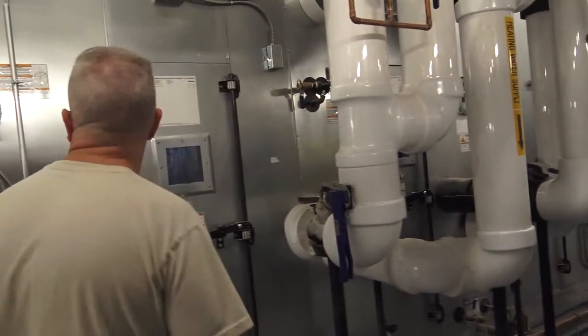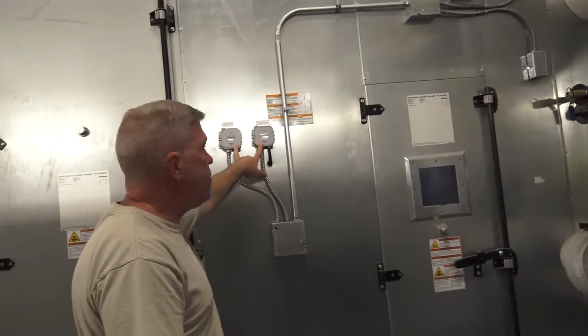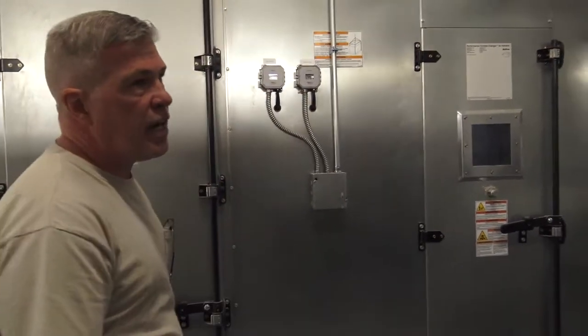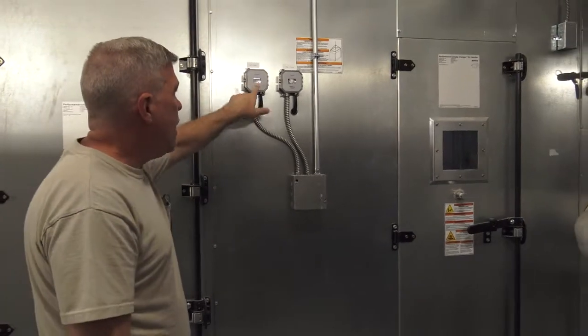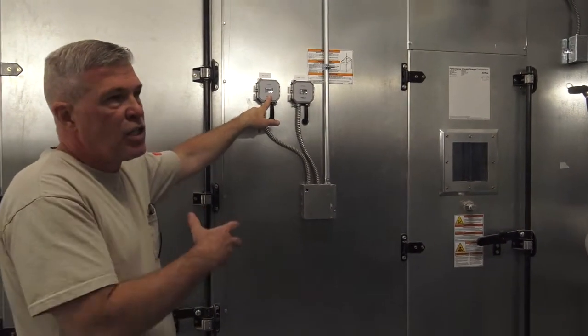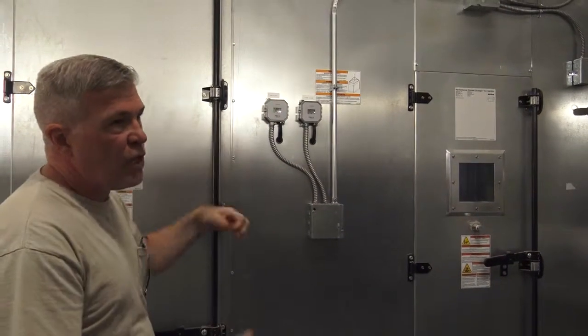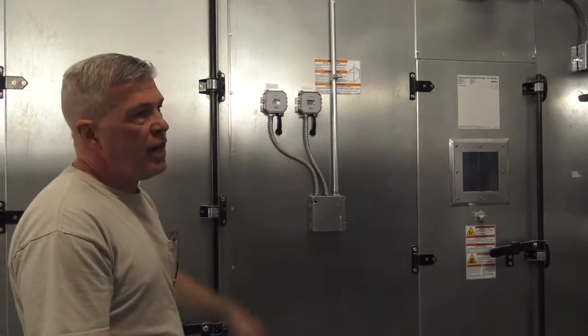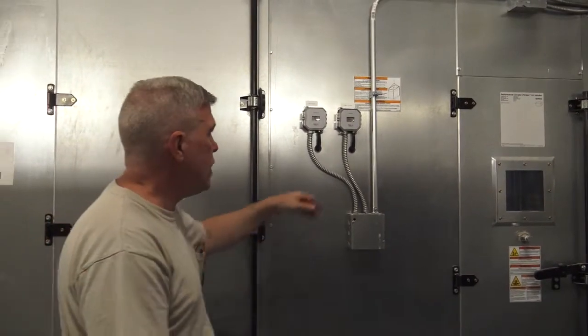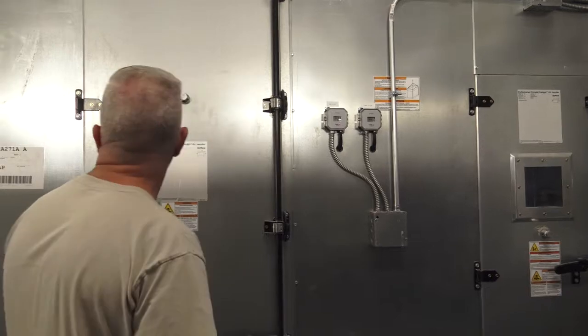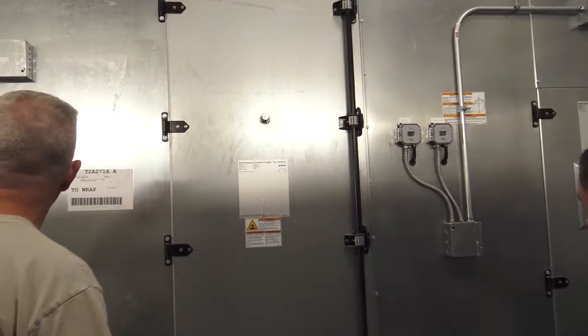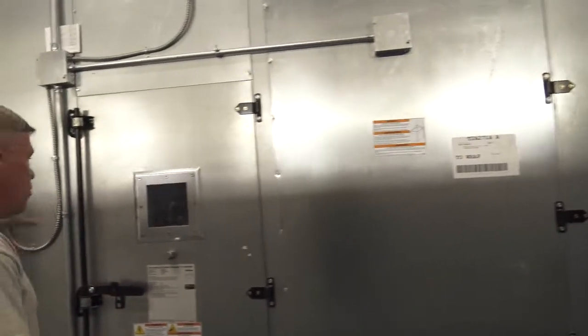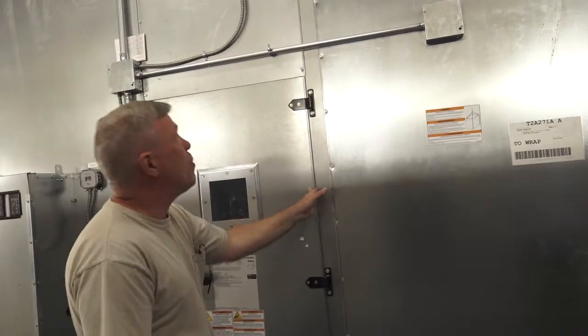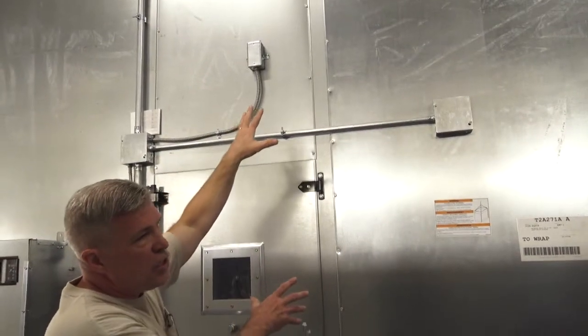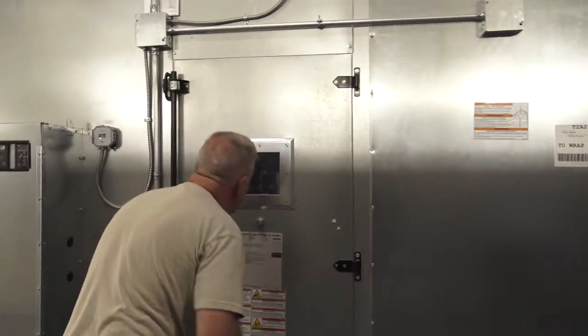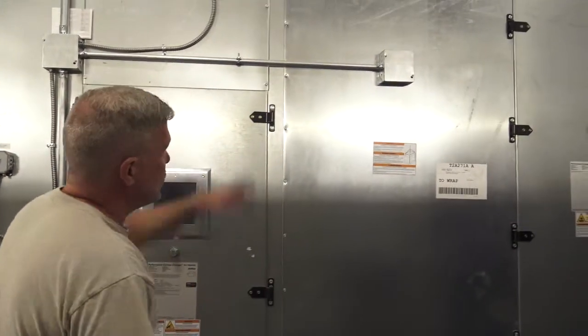So hot water stuff, filter differentials are here. Again, I know you guys primarily change on a scheduled time or something, but you can monitor these. It is on the system, and see maybe at what point, what is your differential when you decide to change them. You can record that, and then maybe you don't have to change them as often, but they're there for your use. And filter sections just in here. Then from about here down is all the return section. Return dampers, outdoor damper, relief dampers are all in this section too. If you look through the window here, you can see the two of them. The outside you can't see just because it's on the other side of the wall.